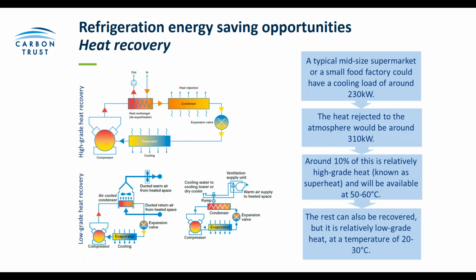The potential savings that can be gathered from heat recovery are a really attractive investment. A typical system has a payback of about 3 to 5 years. This length of time is based on the high initial capital cost of extra heat exchangers, pipework and controls, but the savings overall are really quite significant. The heat recovered is essentially free, and it's a really attractive investment for anyone who uses a significant amount of refrigeration.